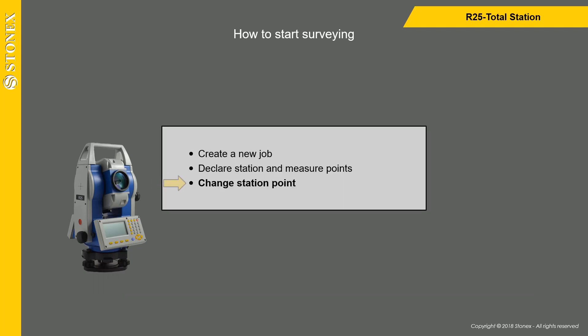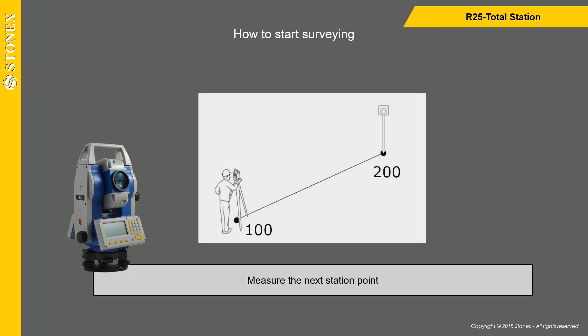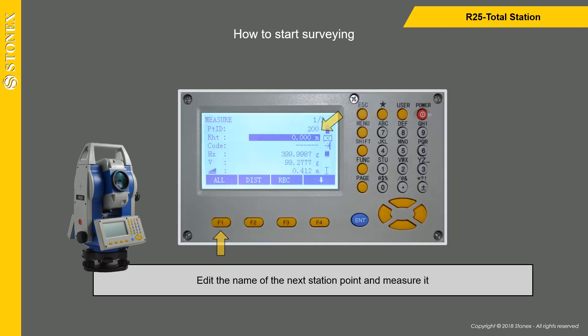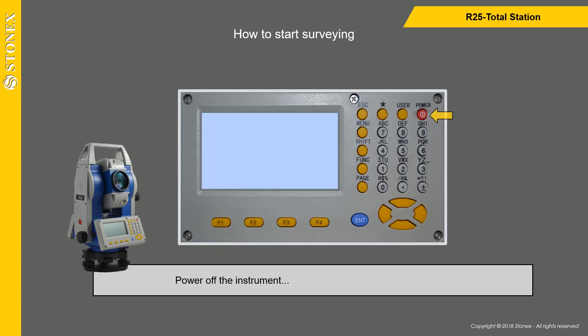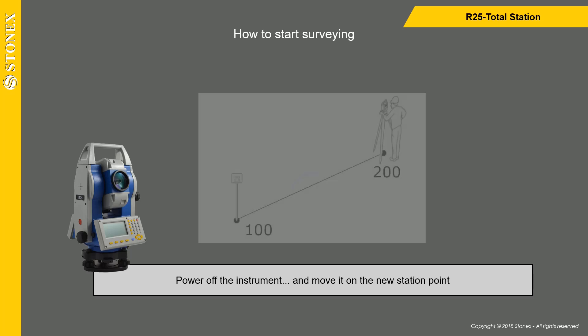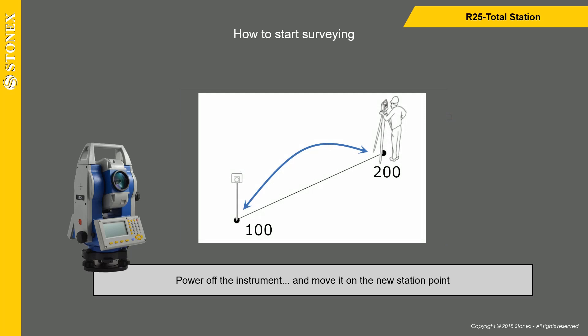To change the station point, measure the next station point. Edit the name of the next station point and measure it. Power off the instrument and move it to the new station point.